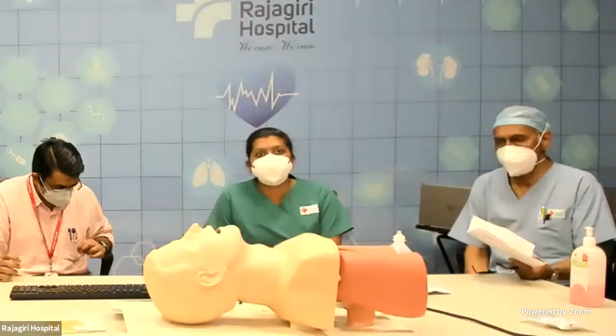So if you're getting a high peak pressure alarm, first you need to start assessing from the patient. Make sure that the ET tube that is placed, the artificial airway, is not kinked or obstructed. And make sure that the patient is not coughing or struggling with the ventilator. After checking the patient, next we come to the connections. Even the HME that is connected for humidification can get blocked with secretions. So make sure that the HME is patent. And coming to the circuit, make sure that there is no water inside the circuit. And at the end, even ventilators can fail.